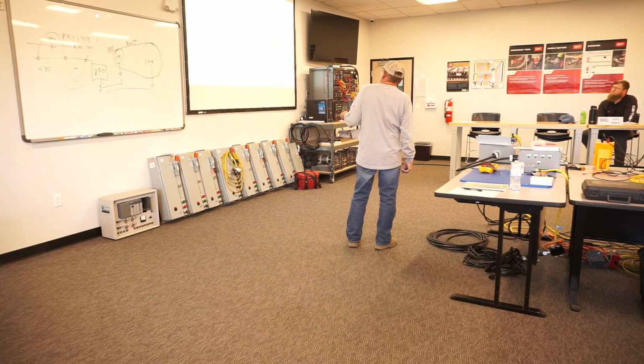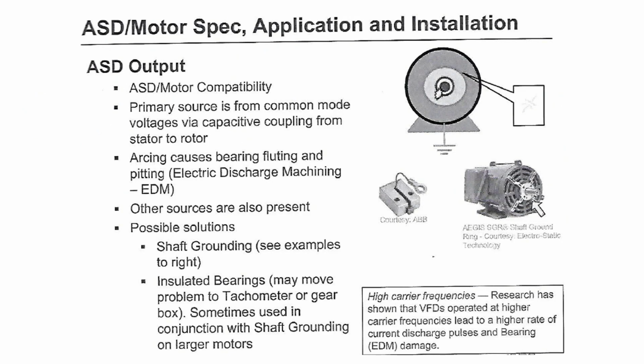A lot of this stuff I pulled out of the ABB manuals. Shaft grounding, insulated bearings, different sources, different methods of preventing the motor shaft bearing problems that we experienced. So, research has shown VFDs operate at higher carrier frequencies, leading to a higher rate of current discharge pulses and bearing damage. And it's been going on for a lot of years. And it'll continue to go on until we do this work properly.